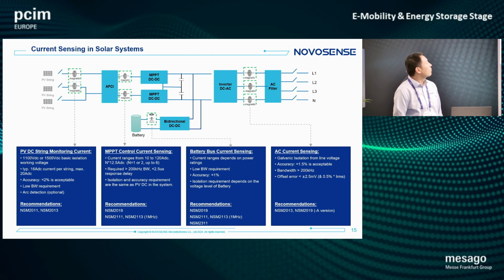For the AC current sensing, it is critical that the current sensor has very low DC offset error. According to government regulations, we need the offset error below 1.5% of the current. So we also have some special products to support this application.